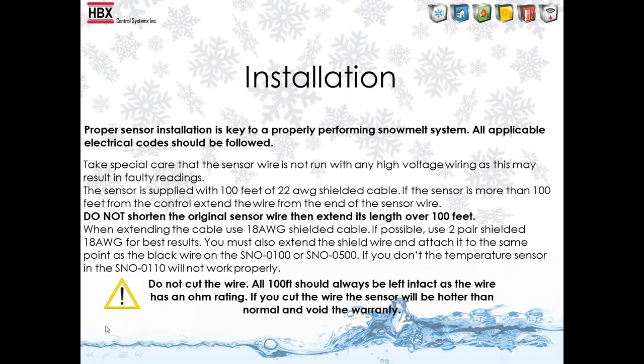If you need to extend it, you can extend it, no problem. You can go up to about 200 feet. Use 18 gauge to extend it, and if you can, use 2-pair shielded. One thing we don't want you to do is run the sensor wire by any high voltage wiring, because it's a digital feedback that we get from that sensor, so it might impair the sensor readings, that's all. So once again, do not shorten the sensor wire. You can make it longer, but do not ever shorten it.